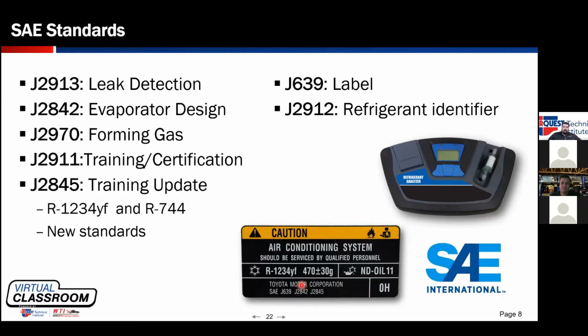J2912 is the standard for refrigerant identification. This is very important. Refrigerant identification is no longer optional when we're dealing with 1234YF. J2970 is a standard for forming gas. Forming gas is a method of leak detection that can be used for 134A or 1234YF.